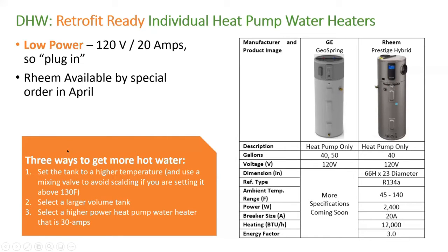One thing to mention about these systems is how to get more hot water, or make sure you have enough hot water stored in the tank compared to gas systems, which have a higher recovery rate. We want to avoid using electric resistance since it uses about 3 times more energy than the compressor. Different strategies for hot water include setting your tank to a higher temperature and using a mixing valve to avoid scalding while getting more hot water, selecting a larger volume tank, or selecting a higher power option at 30 amps.